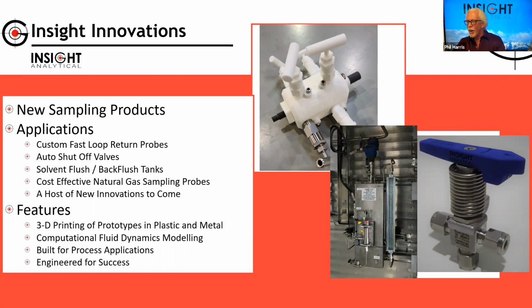So on the bottom right over there, you can see a valve with a spring on it. It's just like this one. And what it becomes is an automated return valve. So you turn it, you want to make it vent, hold it open, let it go, and it shuts off automatically. We'll do those on two-way valves and three-way valves, and we put these all through sample systems now so that if we want this valve to be in a specific position, a specific orientation for most of the time, and only be actuated when someone's holding it, it allows us to control that.